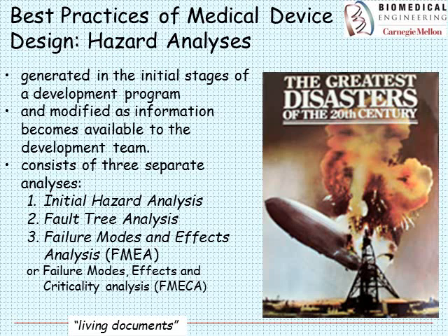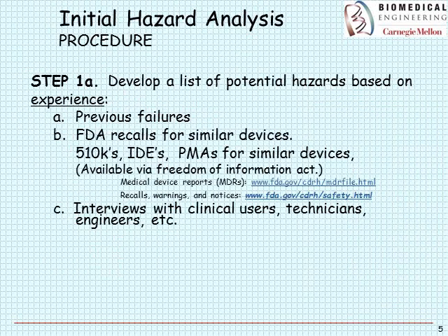The hazard analysis is generated from the very origins of an invention, in the initial stages of a development program. It has multiple stages and is modified as information becomes available. It consists of three separate analyses: an initial hazard analysis, a fault tree analysis, and a failure modes and effects analysis. A variation is called failure modes, effects and criticality analysis, or FMECA. I want to put inventive problem solving in the context of practical scenarios.